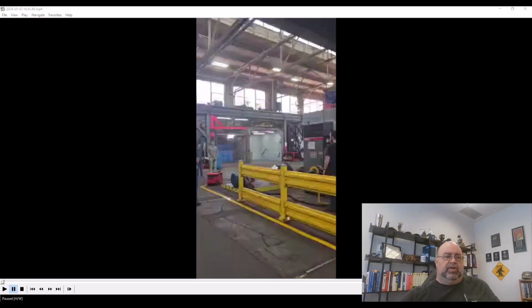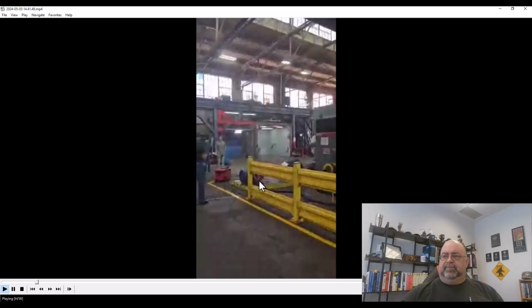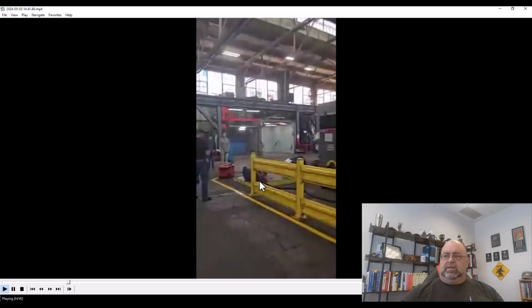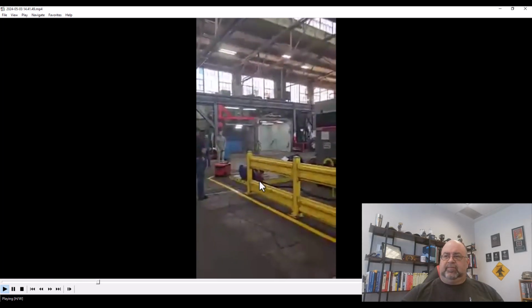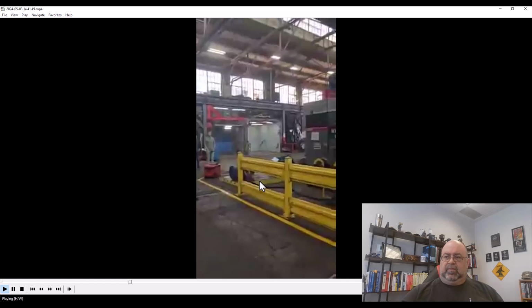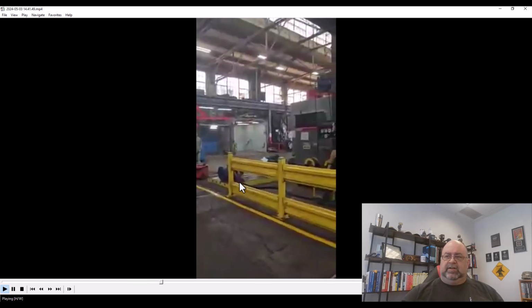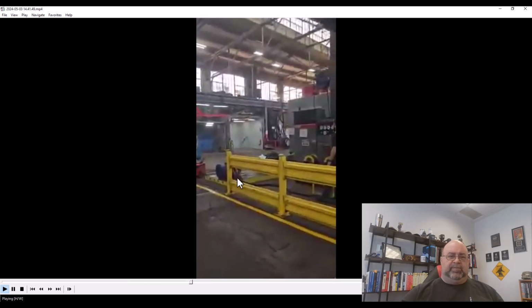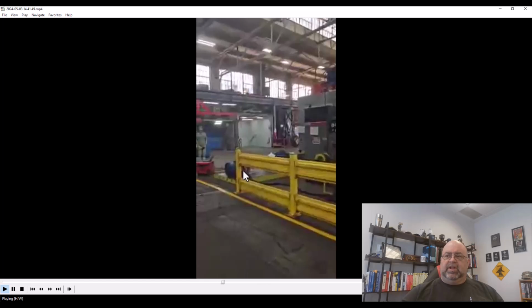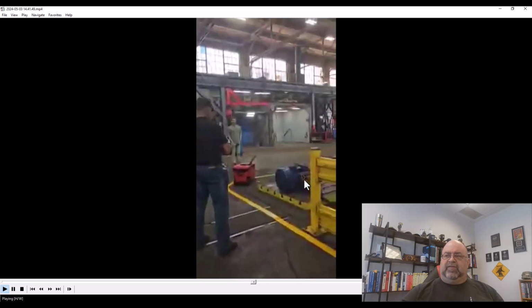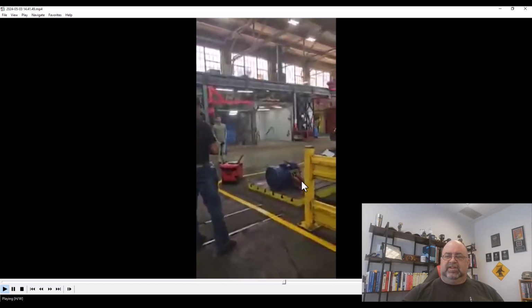So in this case, here's the motor here, and everything's going to lag a little bit, but here's the motor. You watch it, it's running. We're about to start it. Actually, you hear it, lower voltage. As soon as they put it up to full voltage, you hear that snap. You don't see it here, but there's a little fire popping out the side, because this is lagging a bit.